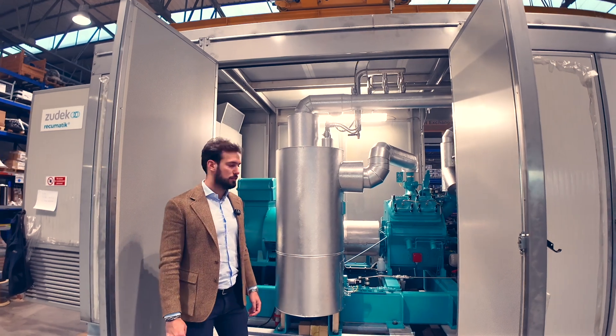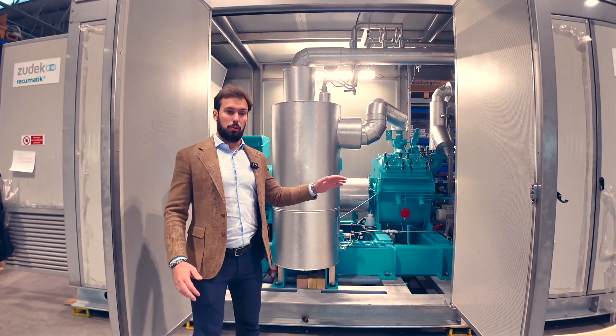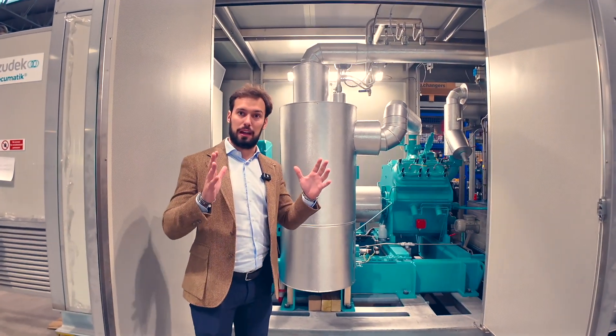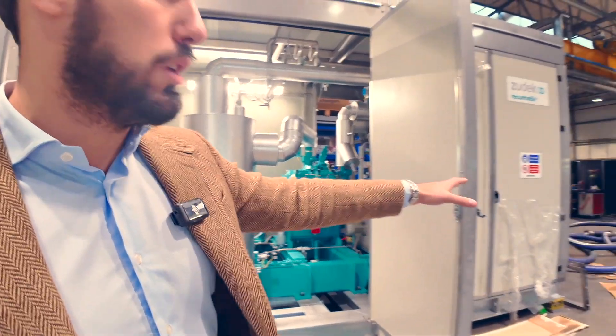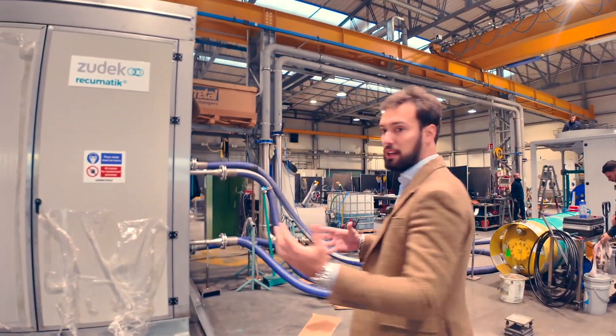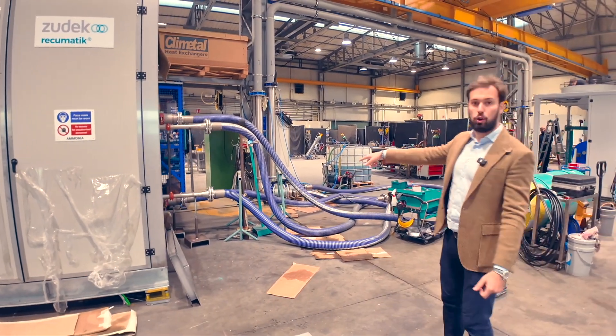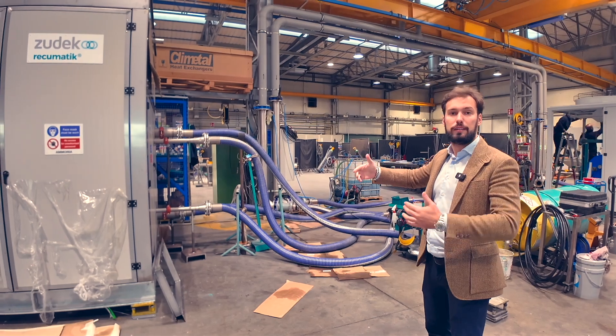Now you've got another unit being made here — this is a heat pump. This is a high-temperature heat pump. How high? This one works at 80°C, but we reach temperatures up to 95°C. We're teaming up with GA for the compressors, so they provide the compressors and we assemble the complete heat pump skid. The heat pump is nearly complete, so I want to show you how we test the unit. We have the full-power test facility in Zudek, which allows us to test all our units — the air-cooled chillers and heat pumps — up to nominal capacity and at really high ambient temperatures. We're connecting cold glycol and warm glycol pipes; we have a dissipation system outside so we can warm up, cool down, and test them at nominal capacity.